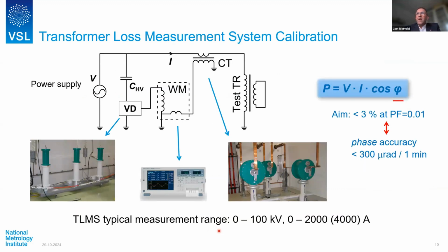So that's what I, again, indicate. The aim for the system here is less than 3% at this power factor, which corresponds to a phase accuracy of around 300 microradian, 1 minute. This is the IEEE requirement. But then, of course, the manufacturers of this kind of test equipment make sure that their equipment meets this requirement, so that will be at least 3 times more accurate. So you end up with roughly the 1% and the 0.3 minutes that I indicated before.